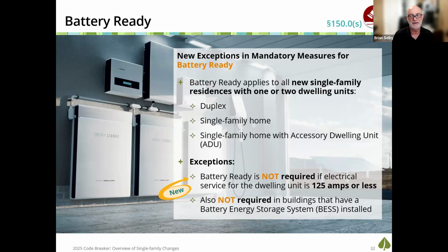Keep in mind that the battery ready requirement requires that the service panel have a 225 amp bus bar rating. So in the situation where the newly constructed space has a much smaller panel design, then it's not required to meet the battery ready requirements.